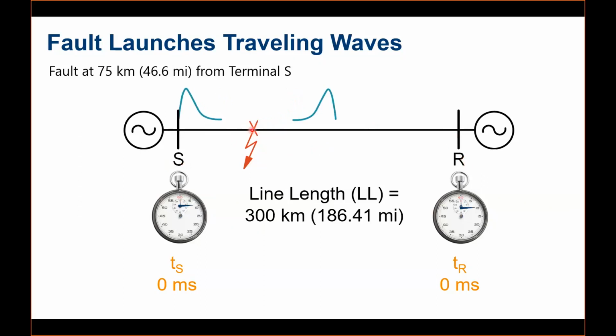So once the fault happens, a traveling wave will be generated on both sides. So it will reach station S earlier than station R. We are talking about microseconds. So the time taken by a traveling wave to travel from this point to station S is Ts, and the time taken by this traveling wave from the point of disturbance to station R is more.